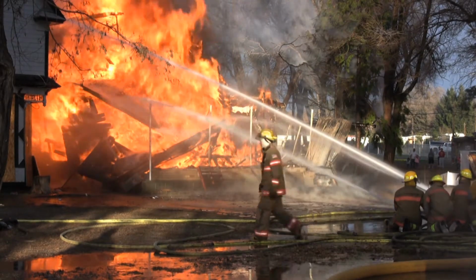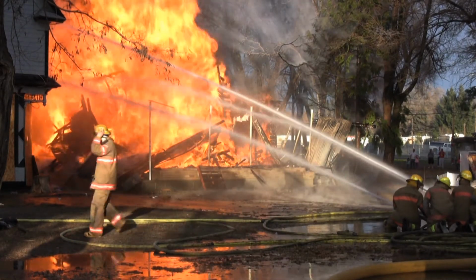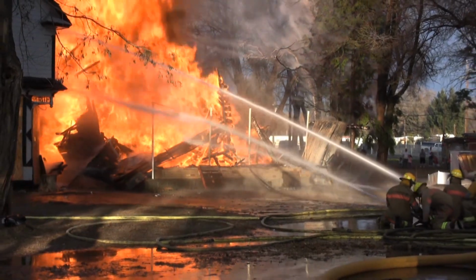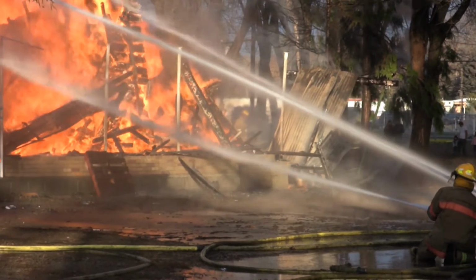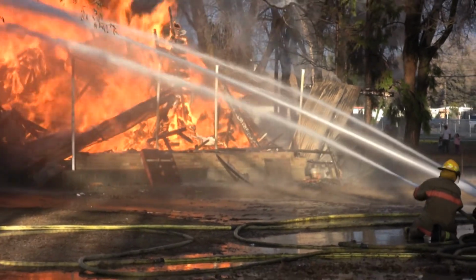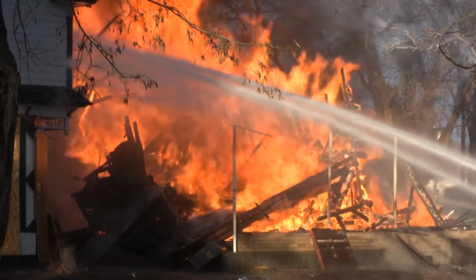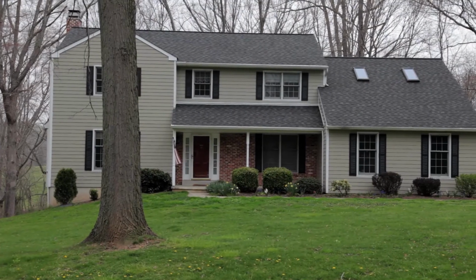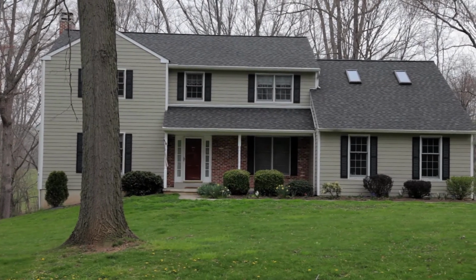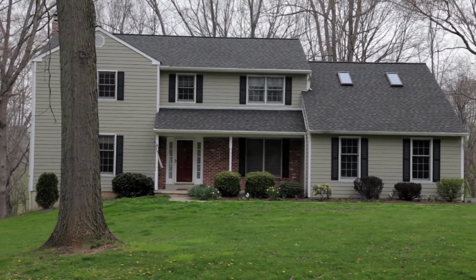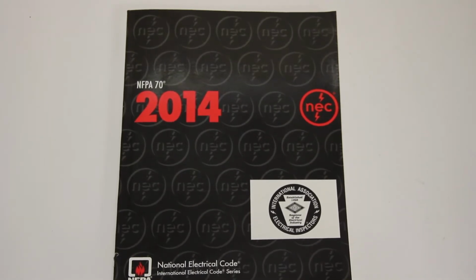According to the U.S. Fire Administration and National Fire Protection Association statistics on residential fires from 2010 to 2012, over 9,600 residential fires were attributed to the electrical distribution system. Electrical safety should be of paramount concern when passing new electrical codes for homes. Since the 1999 edition, the National Electrical Code has recognized that standard circuit breakers cannot protect against arcing faults in all circumstances, and thus has required the installation of arc fault circuit interrupters, also called AFCIs.